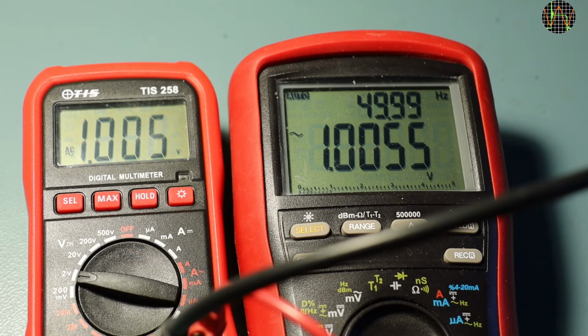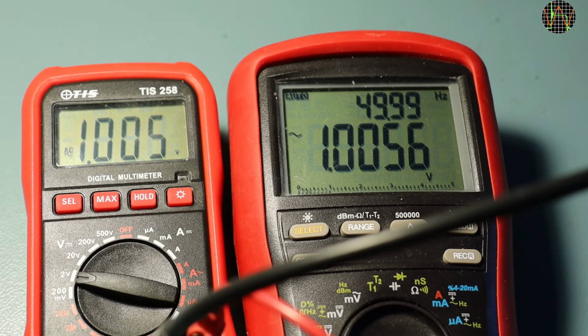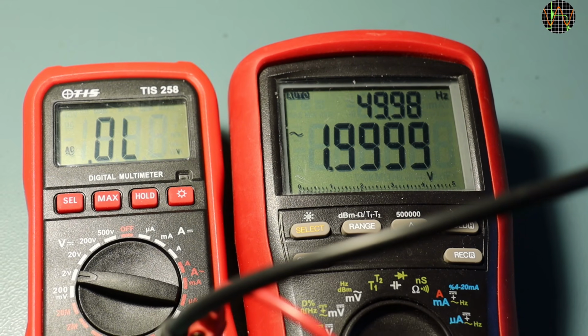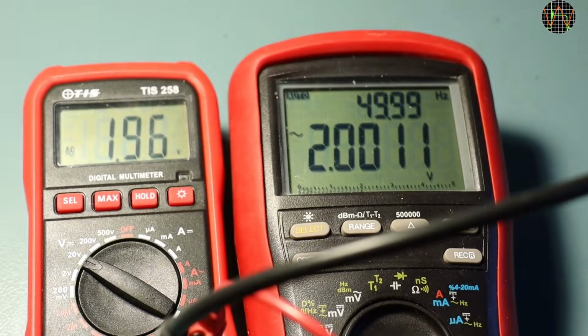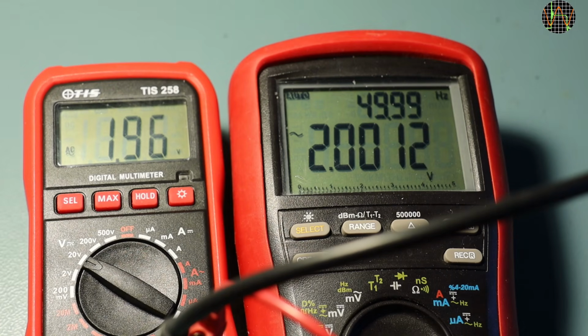Let me demonstrate. Measuring 1 volt AC in the 2 volt range, the TIS-258 is very accurate. If I increase the voltage to 2 volts, I get an overflow, so I have no choice but to select the 20 volt range. In that range it reads 1.96, which is a 2% error, way more than the ±0.8%, but if I add the allowed 3 digits, it would be 1.99, and hence it's still in spec.